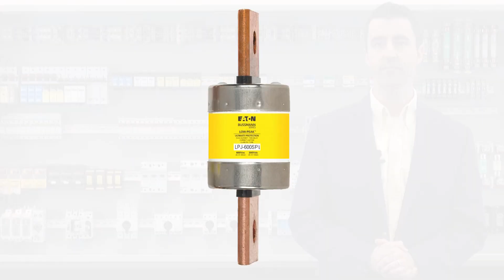Now let's run the same test again, but protect the circuit with a 600 amp Bussmann series Low-Peak LPJ fuse. All other parameters remain the same, but the current will be limited by the fast response of the Low-Peak fuse. In this case, the 600 amp LPJ fuse limited the RMS current let through to a value near 10,000 amps, all within the first half cycle, less than 8 milliseconds.